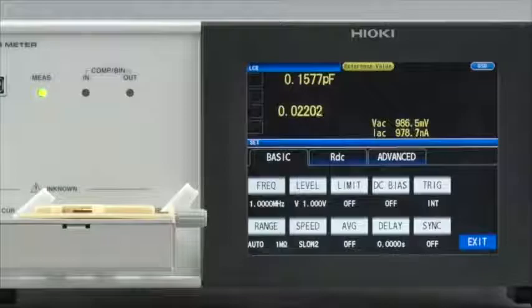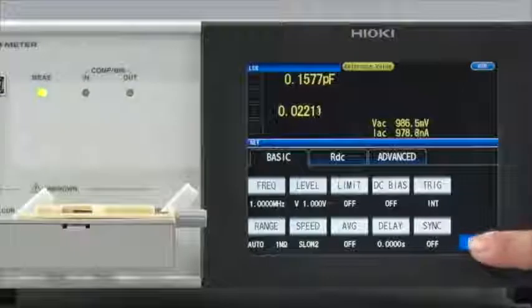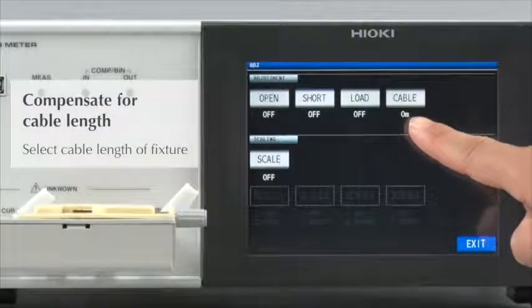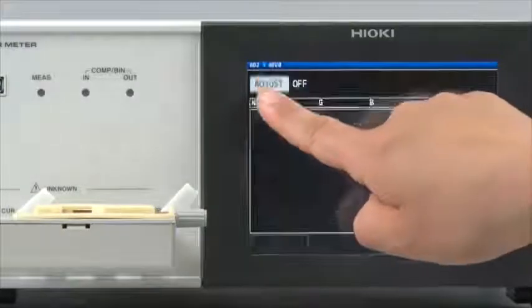Now, let's make open and short compensations. Select the cable length that matches the specifications of the test fixture. First, conduct open compensation.